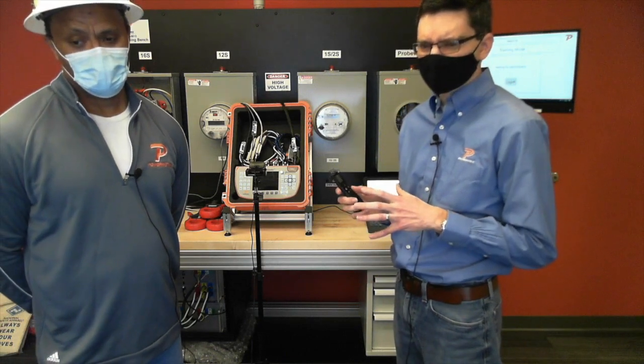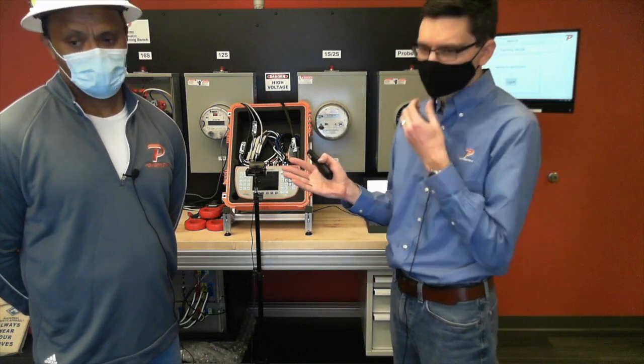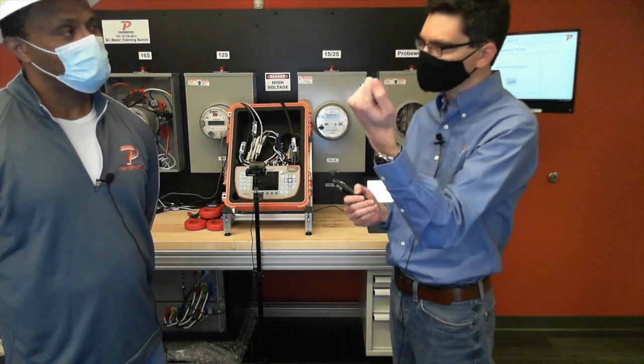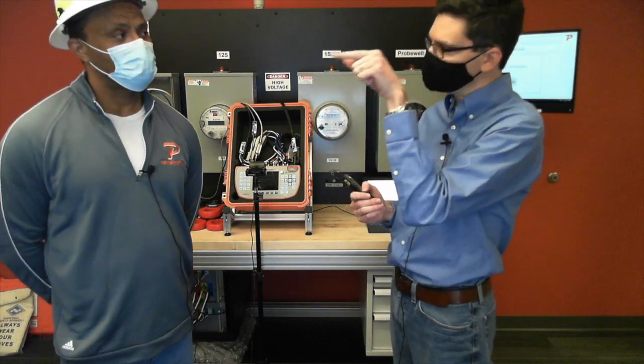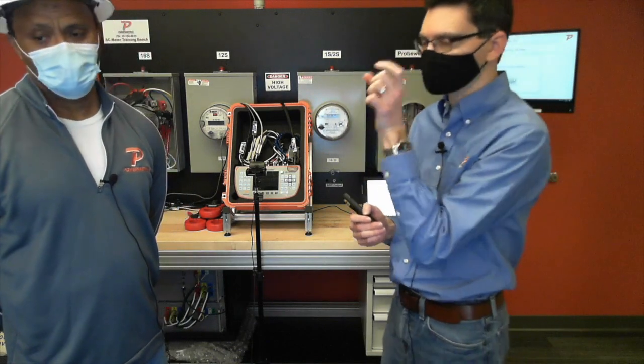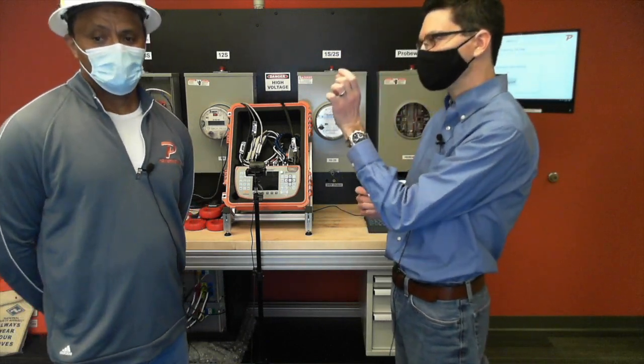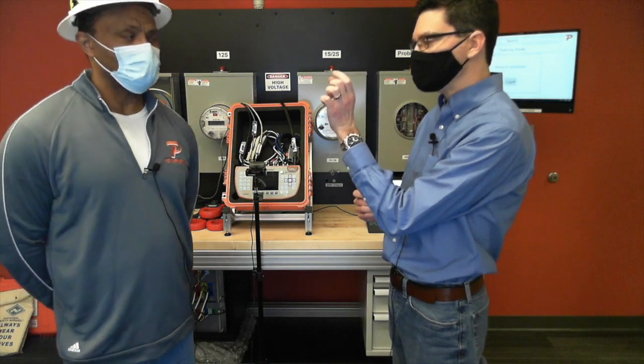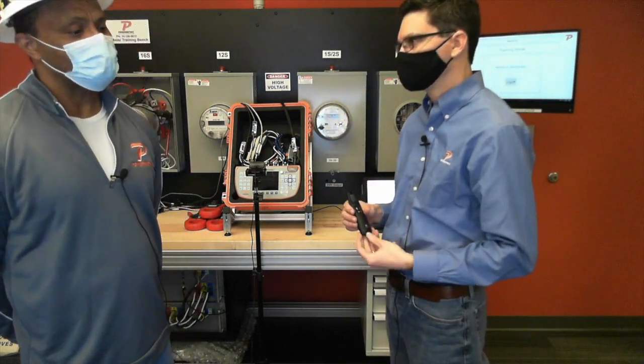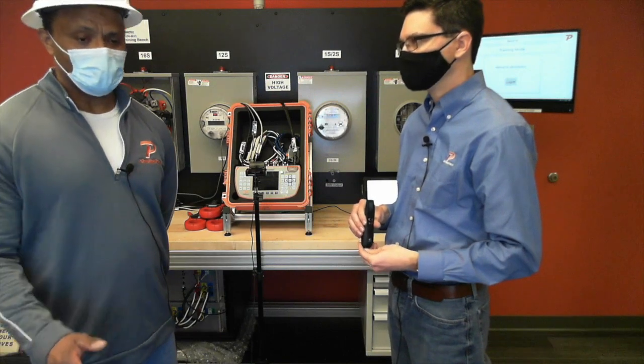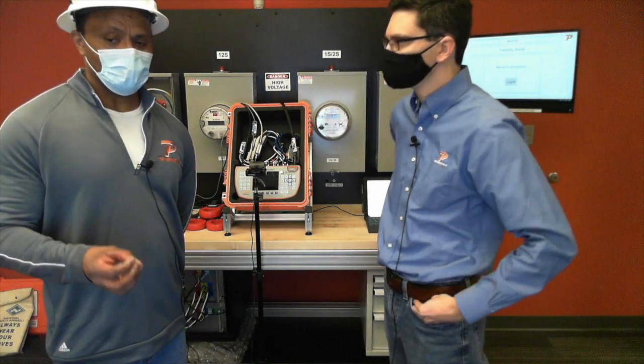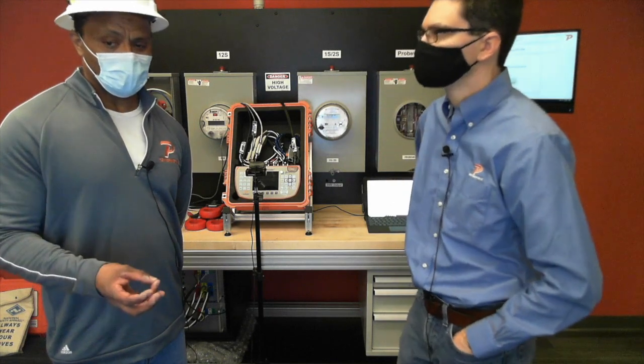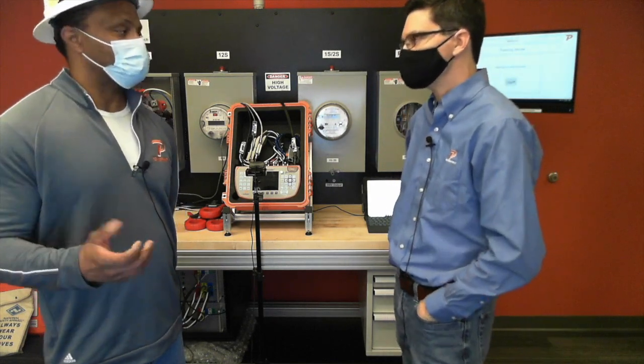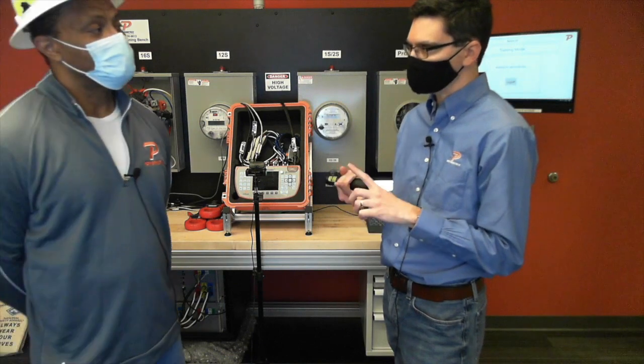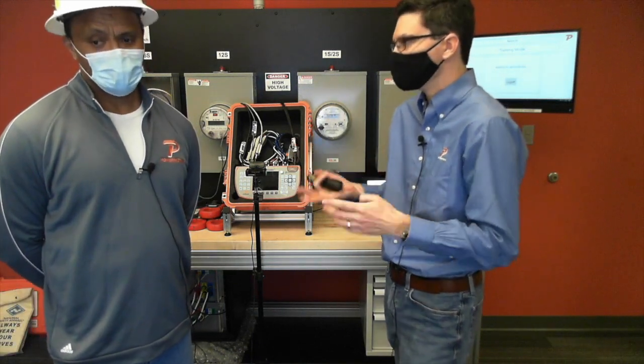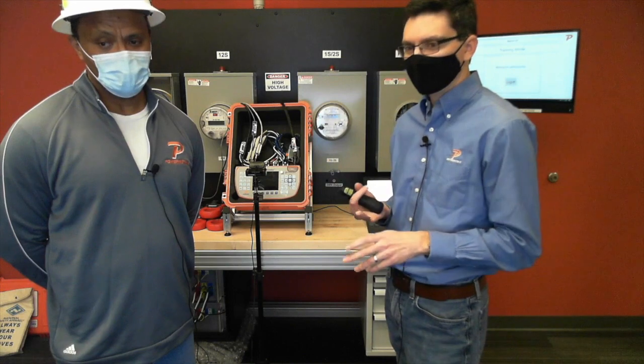I remember you telling me a story about opening up the K-Base cabinet and being able to tell which leg had the problem just by the color of the meter terminal. It was kind of a grayish, bluish, dark color, and you can tell because it's either caused by too much current or because they didn't torque it down correctly. It was a telltale resistance sign, either too much resistance or overburden on the actual meter terminal itself, and it was about ready to go.